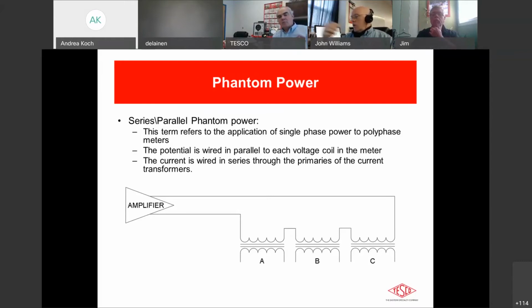Now, of course, we all know there are some differences in the applications for polyphase meters. So really what you want to do is test those meters in a true 3-phase environment. In that case, you don't use the series parallel connection, but you actually have independent channels, 3 for voltage, 3 for current. Everything works independently of one another.